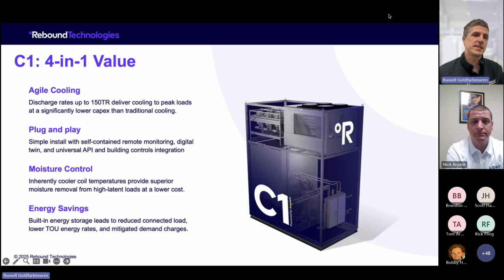What we're bringing to the table that's new is this idea of asymmetry. And what that means is our system is a 25-ton system. It produces ice at 25 tons. The compressor is sized for 25 tons. The condenser is sized for 25 tons. The cost is similar to a 25-ton system. The delivered cooling, though, can be up to 150 tons. And so what we can do is we can run for 12 hours of ice making at 25 tons and then run for 2 hours at 150 tons. And this, when you look at variable loads or volatile loads on the customer side, can deliver a lot of value, and often can result in our system being cost equivalent to a chiller or even cheaper than a chiller. And so we'll get into how that plays out.